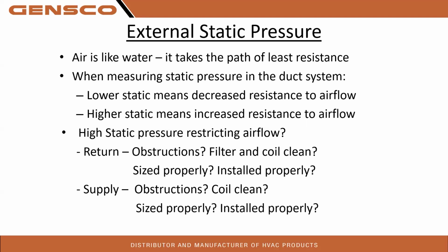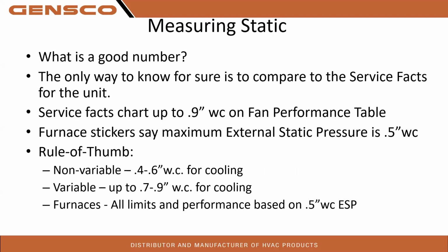And of course, sized properly, installed properly. I don't know how many times the homeowner does not want to pay for that duct modification. And we abide by it. We let them know, we go ahead and install a system, and sure enough, there are issues, right? Stand by your gut. If you think we have undersized ductwork and all the math is showing undersized ductwork, don't install it without fixing it, because that other contractor might go in there and do it cheaper and then have issues and stop answering their phones. They'll eventually call you to come do the repairs and you'll get the service contract. Not always, but I try to do it like that and let people know if they don't want to install the return, they can go ahead and go with somebody else, but keep my number for when they need it fixed.